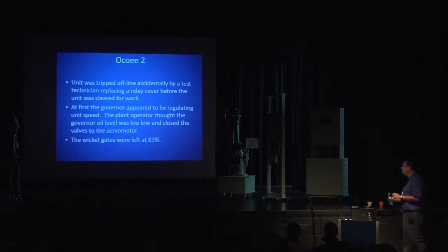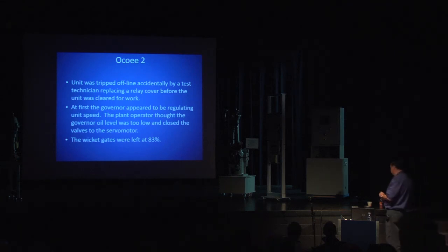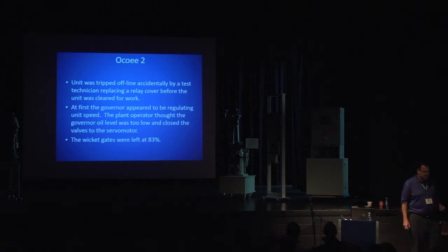we had somebody come in to do some relay checking. They didn't have clearance procedures back then, so basically the unit was running, and he took the plastic cover off the relay. When he put the cover back on, he tripped the relay, and since the governor, or the unit, was tied on line, nobody noticed that the speed was not being regulated.